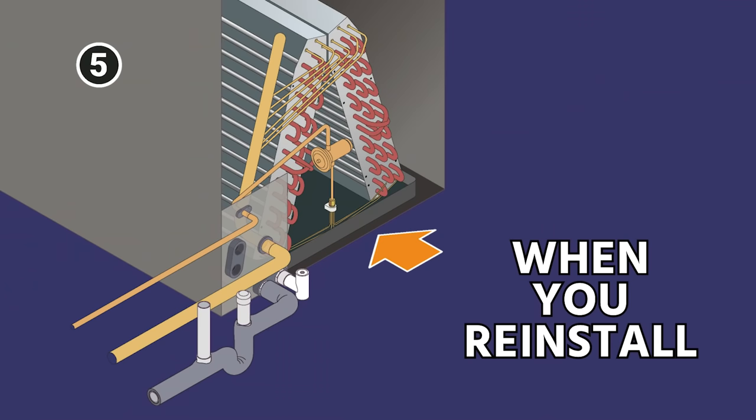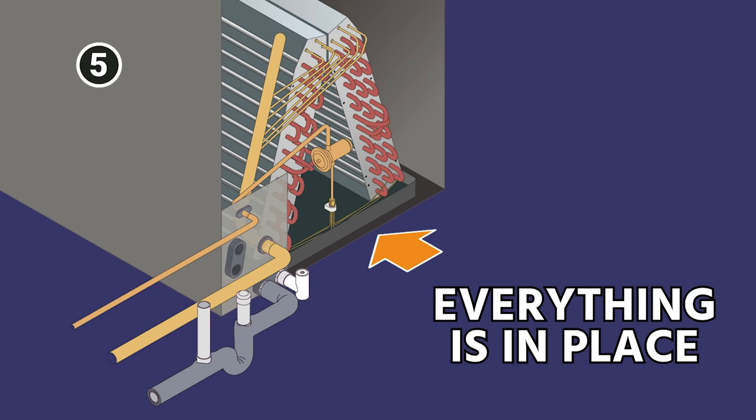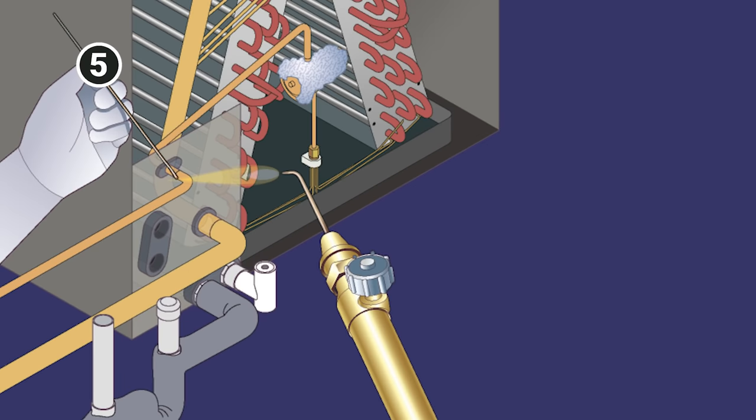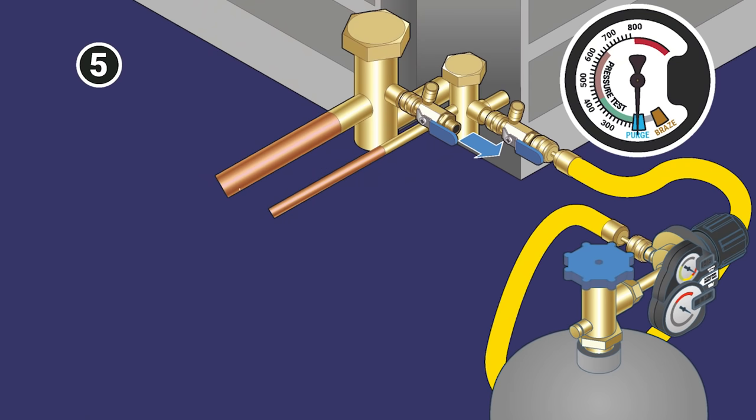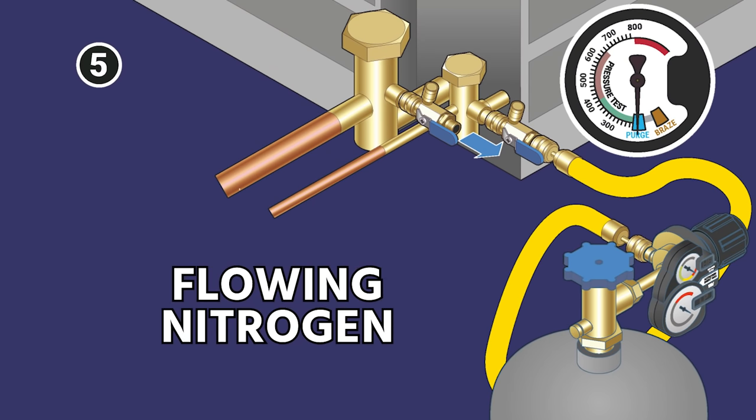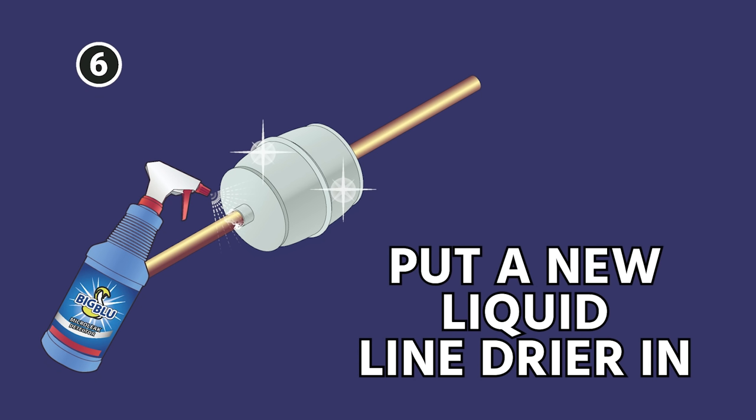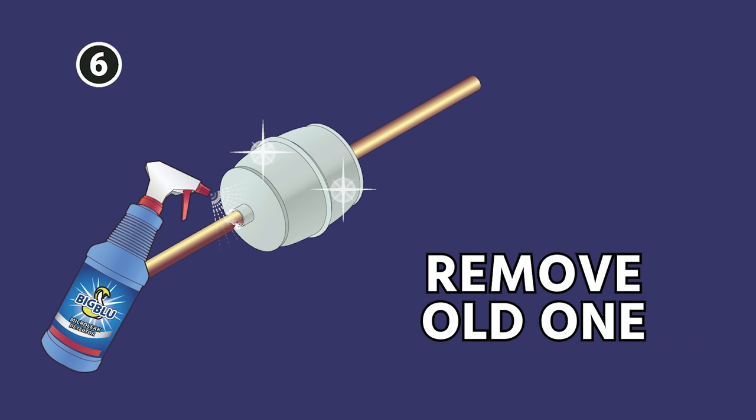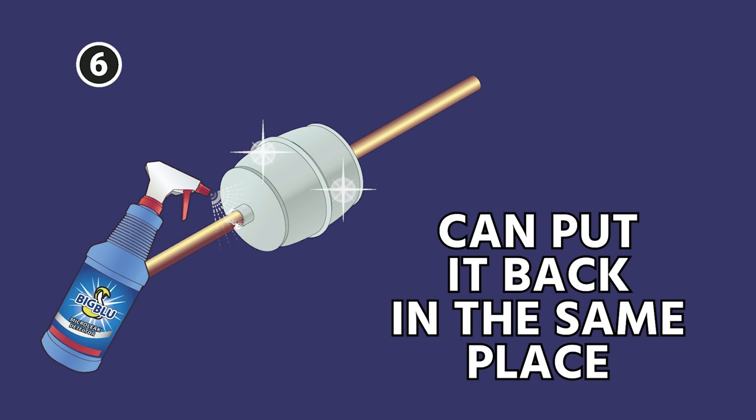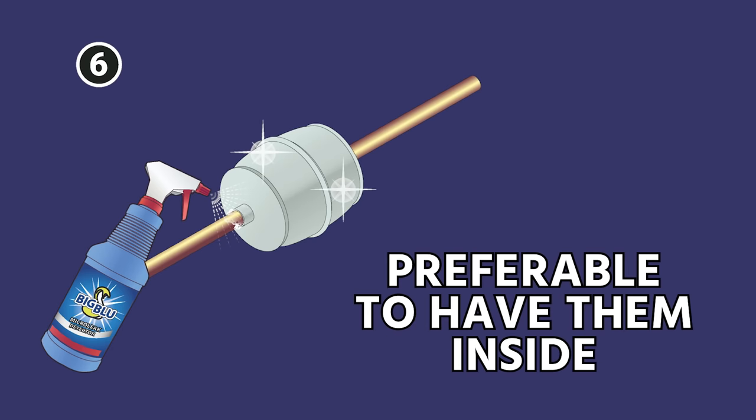When you do reinstall the evaporator coil, make sure that it's level, make sure that all of your proper retaining clips and all those things are put back into place and that everything is slid into place properly. Then you want to go ahead and braze back in your evaporator coil with nitrogen flowing. Now again, you don't want to pressurize with nitrogen. You just want nitrogen to be flowing at three to five SCFH. Make sure that you put a new liquid line dryer in and remove the old one. You can put it back in the same place as the old one, or you can straight pipe the old one and put the new liquid line dryer inside because often they are outside and it is preferable to have them inside.